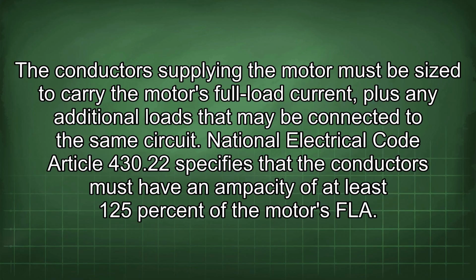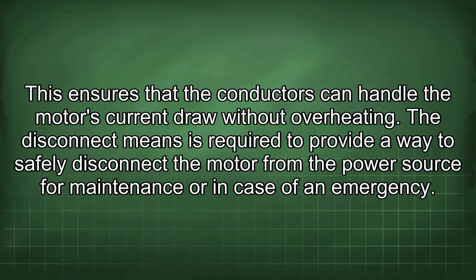National Electrical Code Article 430.22 specifies that the conductors must have an ampacity of at least 125% of the motor's FLA. This ensures that the conductors can handle the motor's current draw without overheating. The disconnect means is required to provide a way to safely disconnect the motor from the power source for maintenance or in case of an emergency.